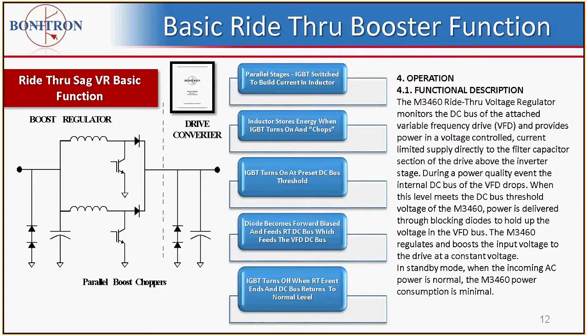The IGBT turns on at the preset DC bus threshold. And once again, that's critical that we know the AC line, because the DC bus is related to the AC line, as we know. The diodes become forward biased and feed the ride-through DC bus, which is connected to the VFD DC bus. When the ride-through event ends, the DC bus returns to normal level from the AC line. Then the ride-through turns off and sits there in a static state.